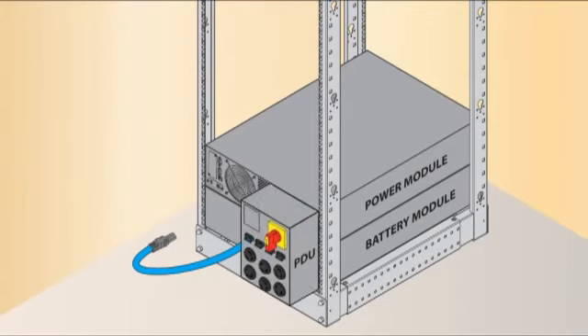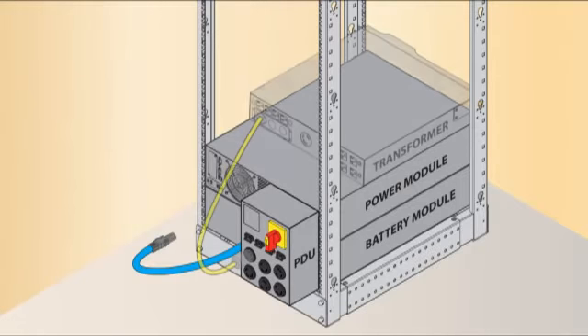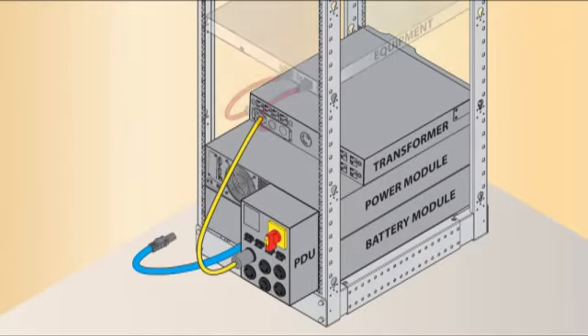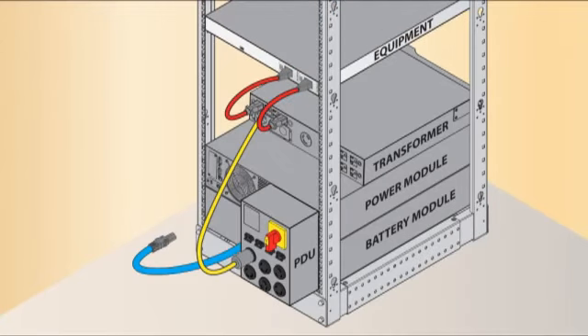First, if your UPS has a detachable PDU, connect it to the power module. Second, if your UPS has a transformer, connect it to the power module or the power module's detachable PDU. Third, connect your equipment to the UPS's output, either on the power module or on the transformer module. Fourth, connect the power module or the power module's detachable PDU to an AC power source.